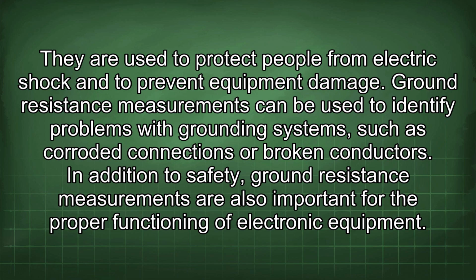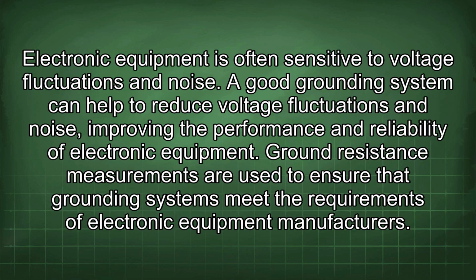In addition to safety, ground resistance measurements are also important for the proper functioning of electronic equipment. Electronic equipment is often sensitive to voltage fluctuations and noise. A good grounding system can help to reduce voltage fluctuations and noise, improving the performance and reliability of electronic equipment. Ground resistance measurements are used to ensure that grounding systems meet the requirements of electronic equipment manufacturers.